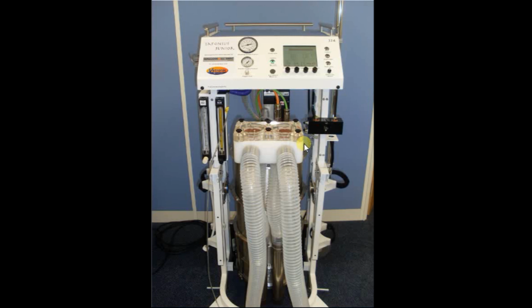Okay, we're just going to look at the patient circuit in a little more detail. As we talked about before, we have the valve block here with the inspiratory side here, expiratory side here, running down to the Y piece. And I want to point out one fairly innocuous but very, very important feature of the machine, which is a little tube that runs down here and, as we'll see, connects to the Y piece at the front. This tube is the patient pressure sensing tube, and it's very important to the perfect function of Tafonius.